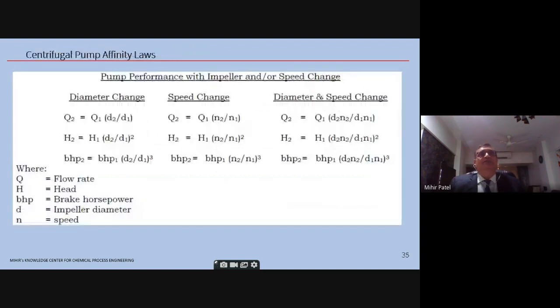Now, centrifugal pump affinity laws. So, as is known, the flow rate varies proportional to diameter as well as speed of the pump. The head varies as the square of the diameter or speed changes, and the power varies as the cube of the diameter or speed changes. So with this, if you have any speed change in the pump, you can automatically calculate the other parameters. These are called the affinity laws.